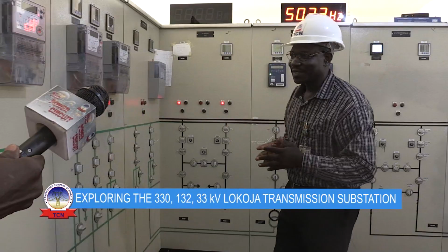We also have check meters. They are at the back of the panel. They are not to be seen, but they are check meters that confirm whatever values this one is giving. And in addition to that, the check meters, they are smart. So the distribution company that installed the check meters is able to read the energy that we are giving out in real time. So at the end of the day, we compare with what we have here, and we expect that they should tally. If there's any disparity, then we begin to ask questions.